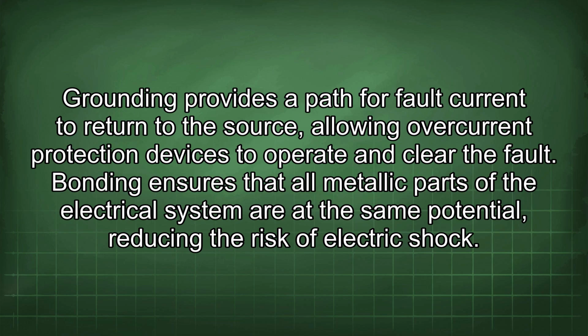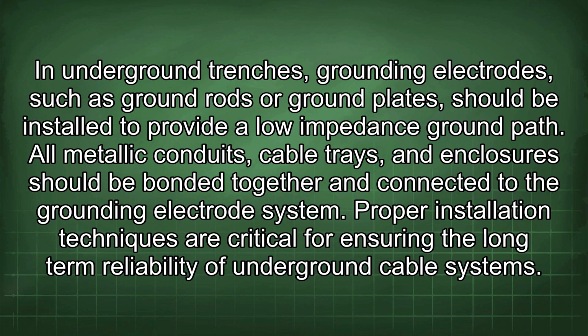Bonding ensures that all metallic parts of the electrical system are at the same potential, reducing the risk of electric shock. In underground trenches, grounding electrodes such as ground rods or ground plates should be installed to provide a low impedance ground path. All metallic conduits, cable trays, and enclosures should be bonded together and connected to the grounding electrode system. Proper installation techniques are critical for ensuring the long-term reliability of underground cable systems.